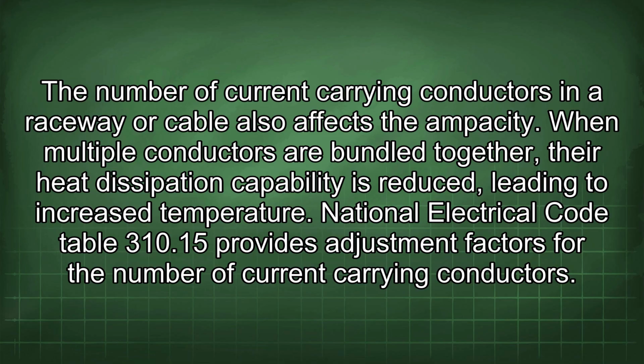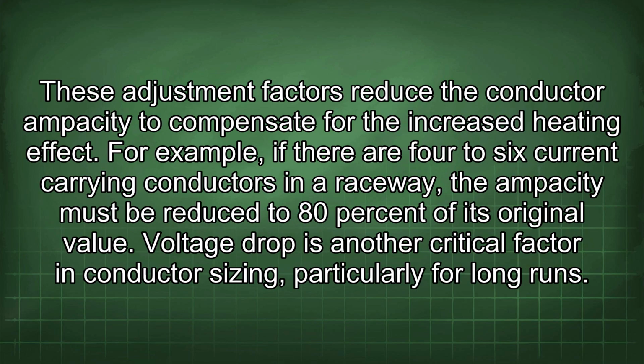The number of current carrying conductors in a raceway or cable also affects the ampacity. When multiple conductors are bundled together, the heat dissipation capability is reduced, leading to increased temperature. National Electrical Code Table 310.15 provides adjustment factors for the number of current carrying conductors. These adjustment factors reduce the conductor ampacity to compensate for the increased heating effect.